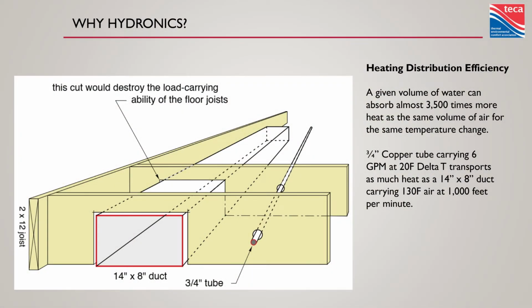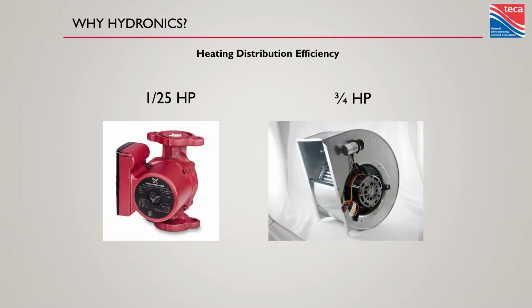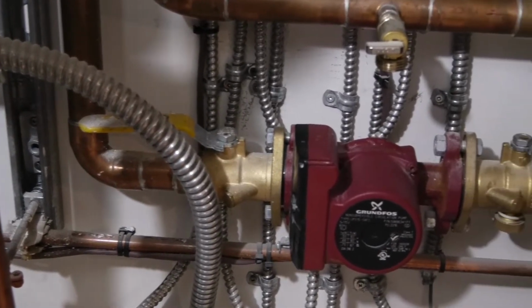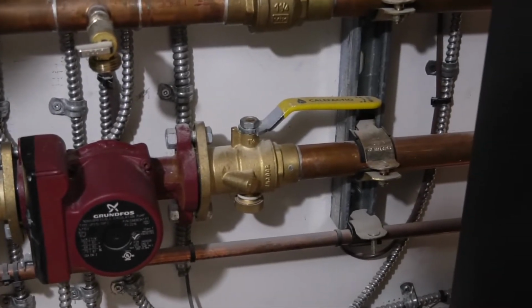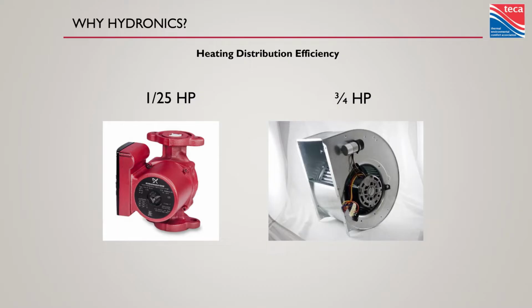So there's a quick slide. Some of you guys have probably seen this before. 3/4 inch copper pipe can replace a 14x8 duct undergoing the same temperature change as far as heat transfer capability. We don't think of air as heavy because we're all swimming in it all the time, but it is. We use a lot of energy to move air around. In a typical house, we're talking a 3/4 horsepower blower motor or a 1/25 horsepower circulator pump to do the same heat delivery. You take a gas furnace and a gas boiler with the same combustion efficiency, that's neck and neck, but how are we delivering that heat? We can do it much more efficiently with hydronics. And even those 1/25 horsepower circulators are kind of going by the wayside now with modern ECM pumps. So the technology is advancing rapidly.